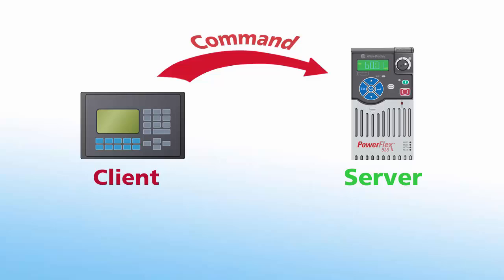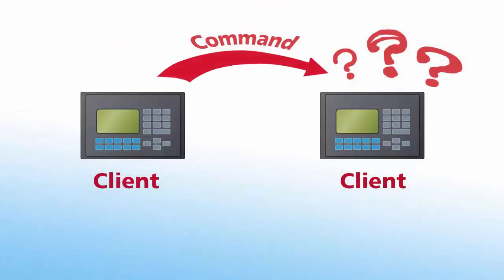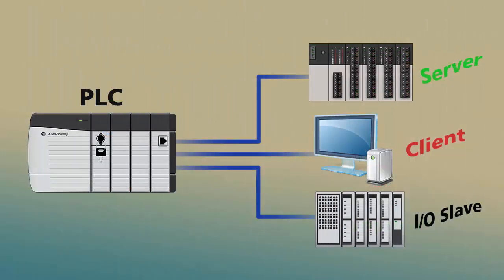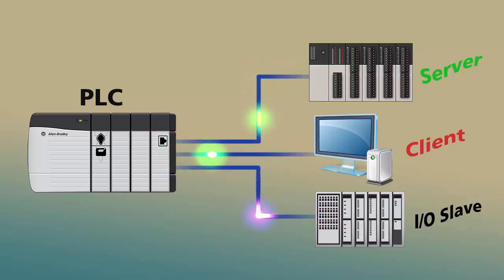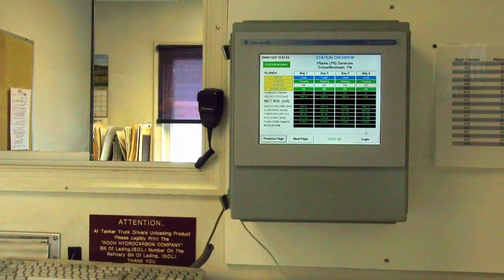Clients are devices that initiate communications and servers respond. Clients cannot talk directly to other clients, and servers don't talk to other servers. It's possible for a PLC to act as a client, a server, as well as an I/O messaging master simultaneously on the same network, communicating with various server devices and clients while controlling remote I/O devices as applications demand. I/O message communications are given higher priority by the processor, while client-server data messaging is given lower priority.